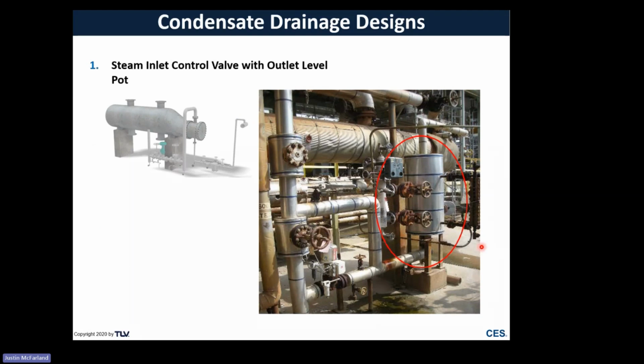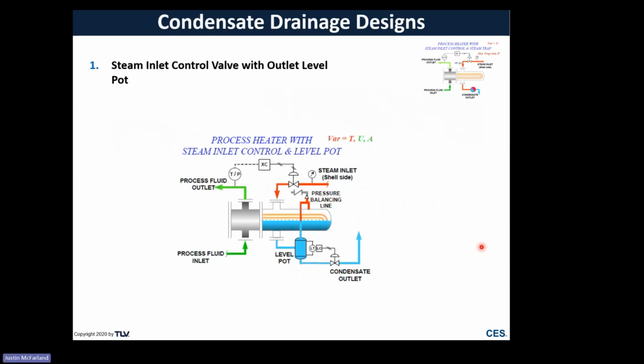Another type of design is a steam inlet control valve with an outlet level pot. So you could think of this as basically an electronic steam trap. It's really all it is. Got an outlet control valve, got a level pot, but all this is designed to do is look at a level as that bounces up and down or is held at a certain level inside a level pot. But still we've got an inlet modulating control valve, and as long as there's positive differential pressure, then this will drain and it will act just like a steam trap and everything's going to be great. But again, as soon as we have negative differential pressure, then there's problems, just like with the last scenario.